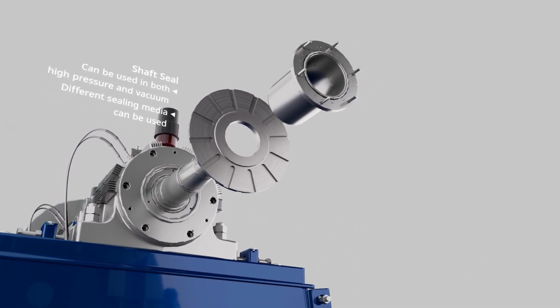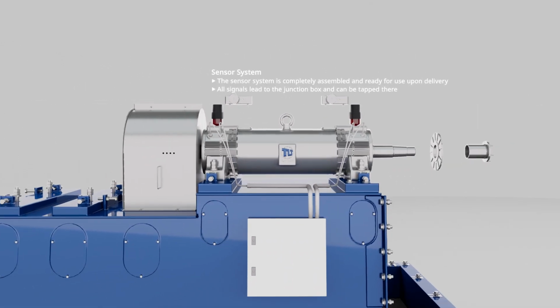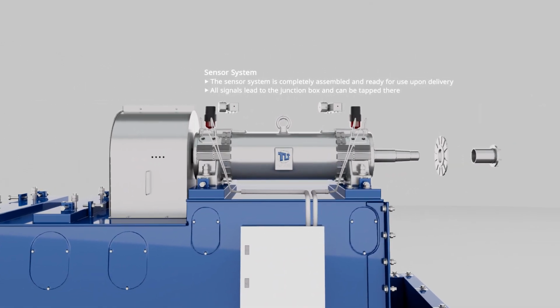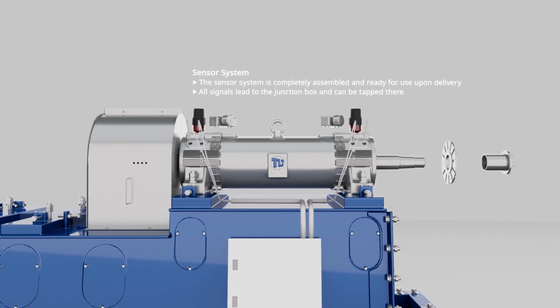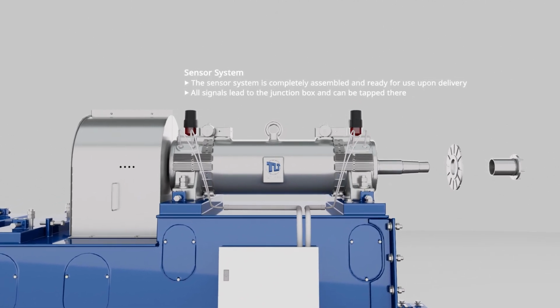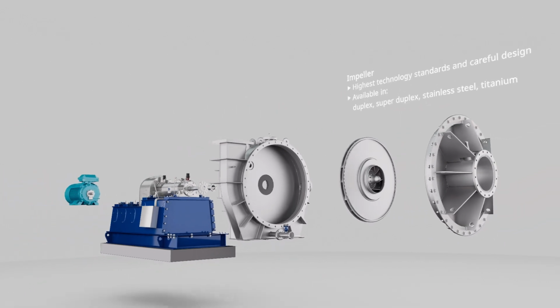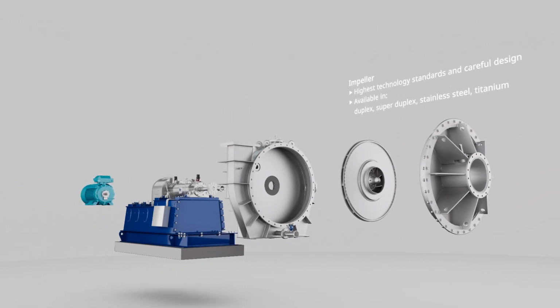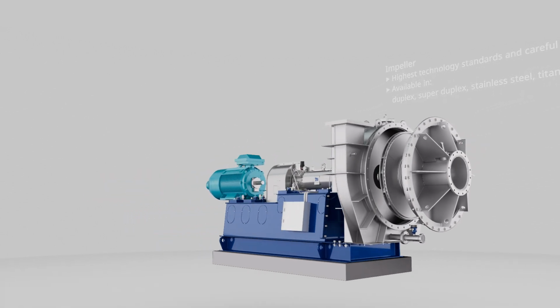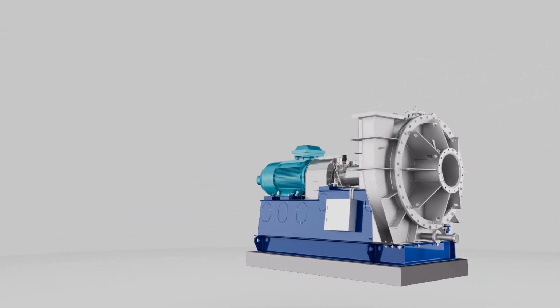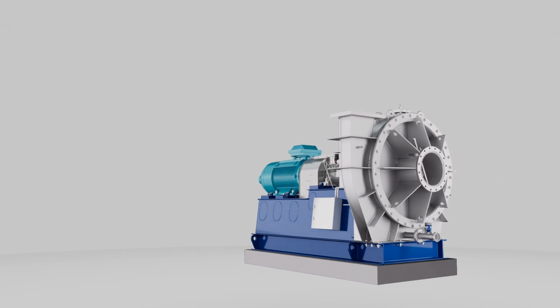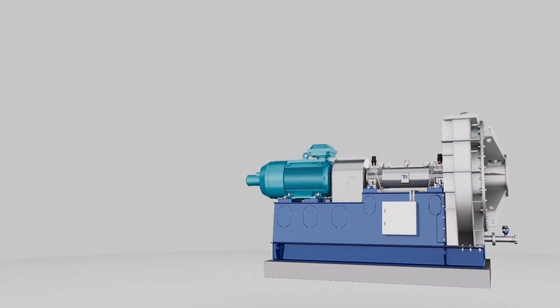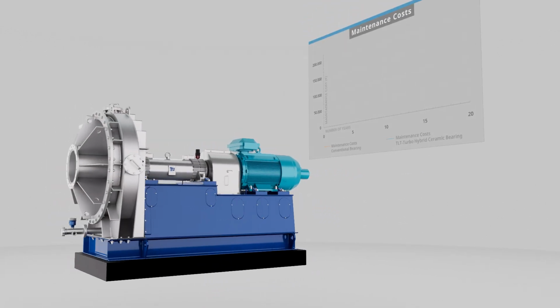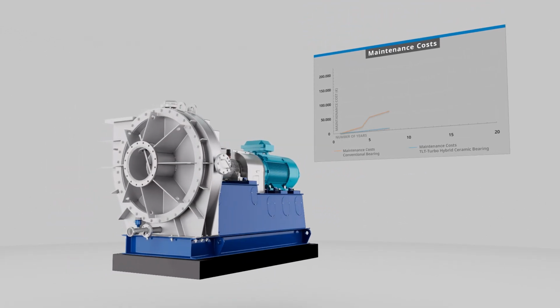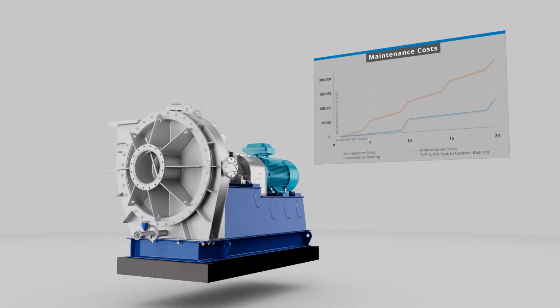The bearing temperature and vibration values are continuously monitored by sensors to ensure that any irregularities are detected at an early stage. The bearing's outstanding running properties, even in case of inadequate lubrication, means that service and maintenance measures can be suitably planned and coordinated with the maintenance intervals of the system. The TLT Turbo MVR design is set apart from other products on the market by its impressively high availability, outstanding efficiency, and because there is no oil system, much lower maintenance costs.